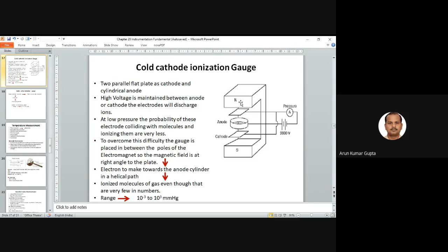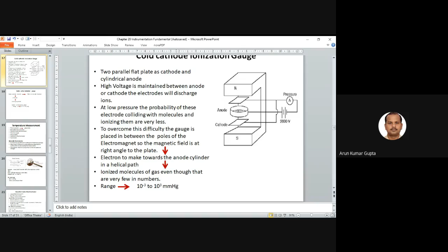At low pressure, the probability of electrons colliding with molecules and ionizing them is very low. To overcome this difficulty, the gauge is placed between the poles of an electromagnet so that the magnetic field is at right angles to the plates. The electrons should move towards the anode with high velocity so that ionization takes place properly. That's why we maintain everything under the electromagnetic field. The electrons move towards the cylindrical anode in a helical path and ionize molecules of the gas, even though they are very few in number. The range of pressure we can measure is 10 to the power minus 3 to 10 to the power 3 mmHg.